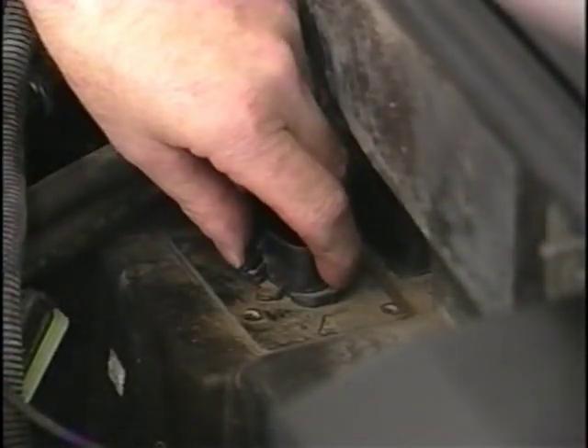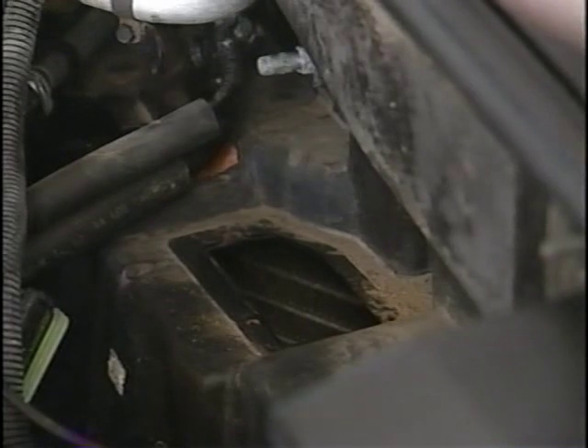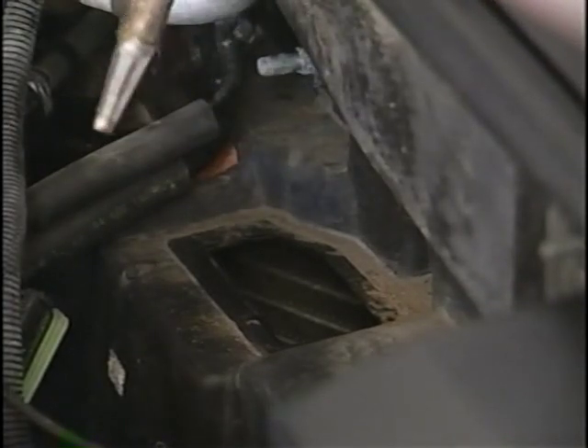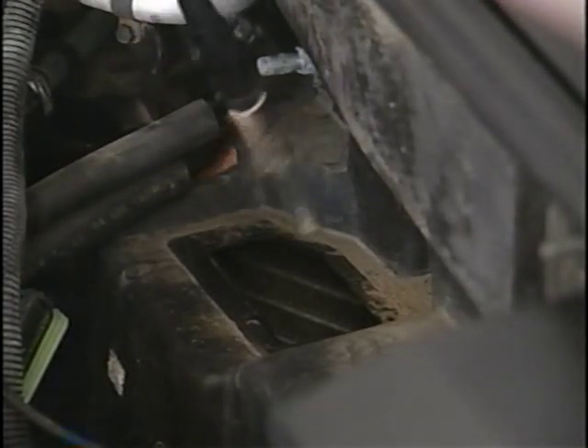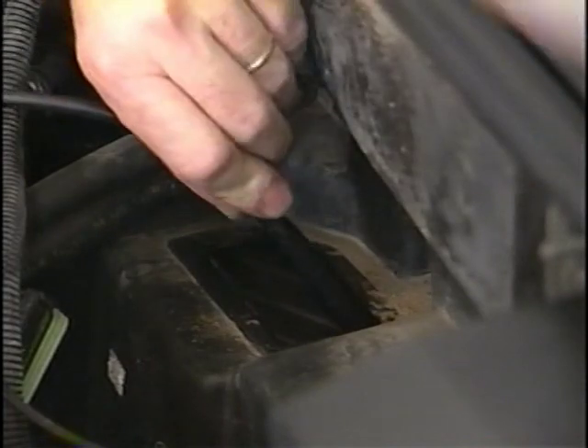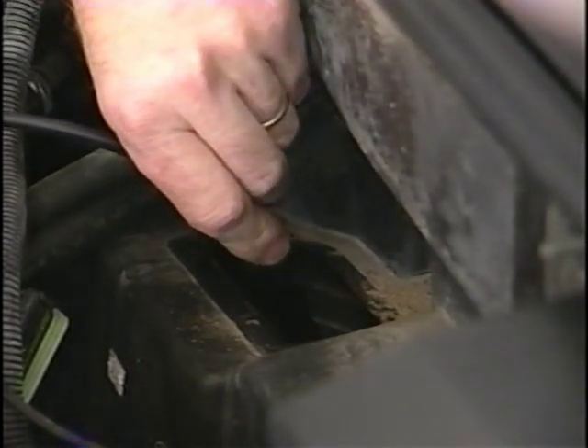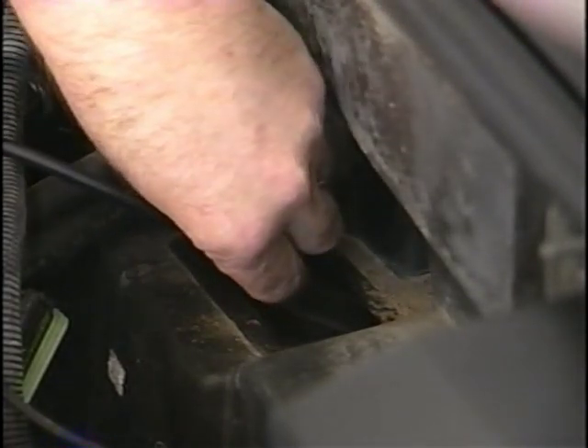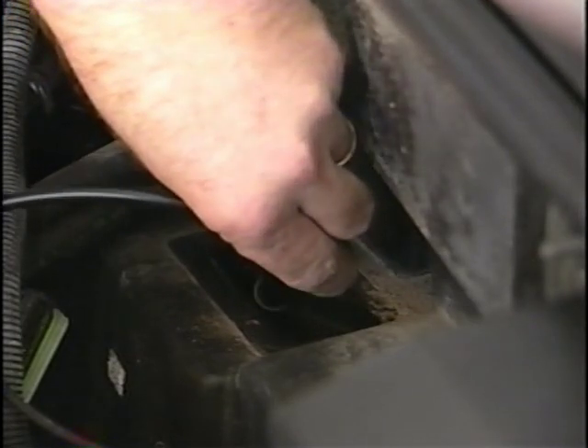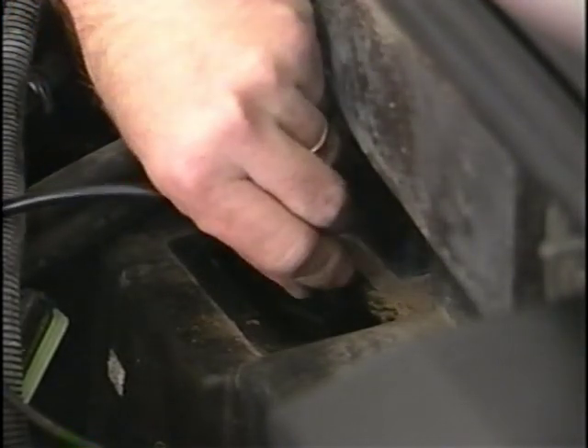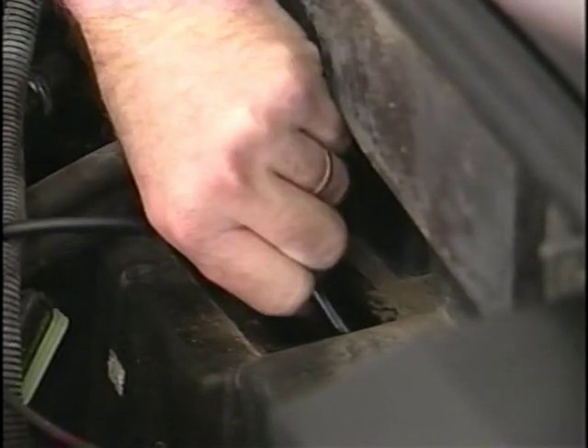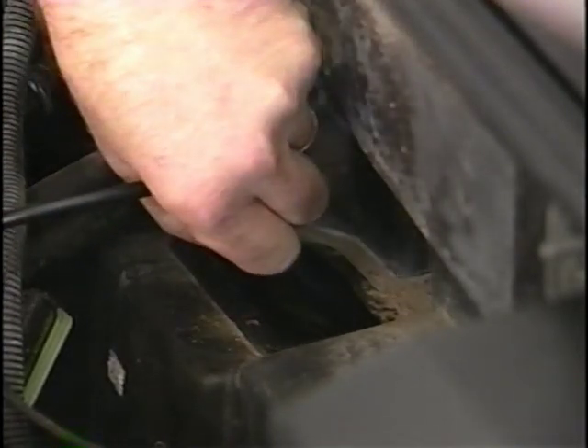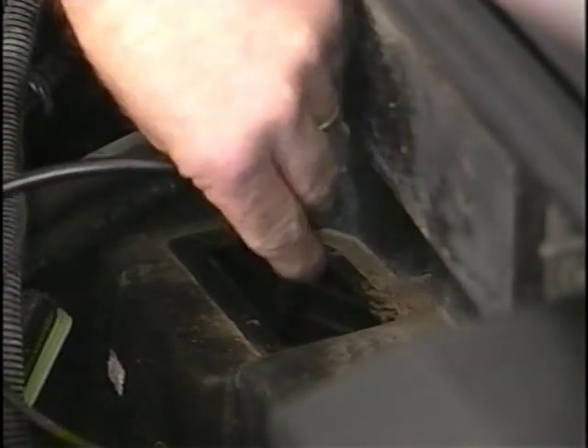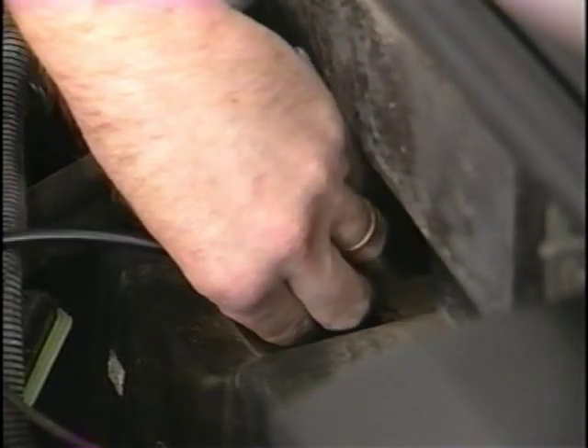Okay, to check for an evaporator leak, the best thing is to get the resistor out of the way, and that gives you access right to the core itself. First look at it, see if there's anything obvious. If not, take the leak detector and go all around the core with it. You can go all over the front of the core and over to the corners and up the sides and see if it picks up anything anywhere.